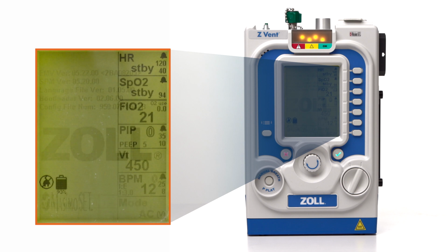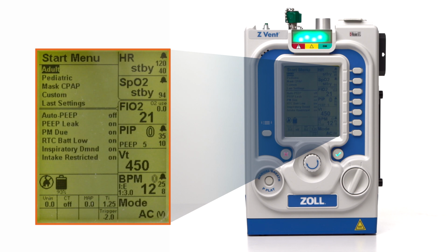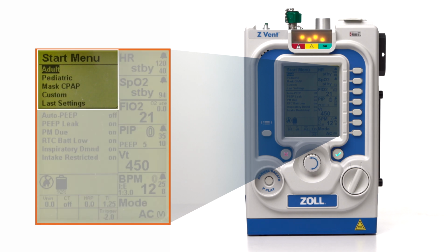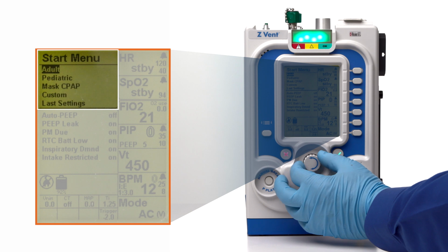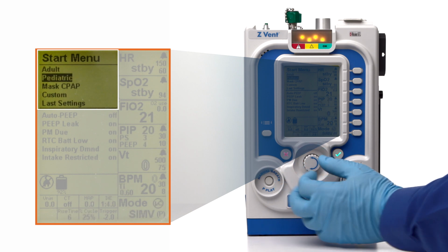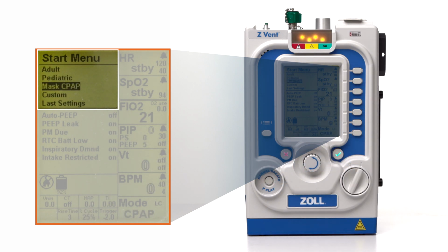If the self-check passes, the start menu will display on screen at the top left, and the LED array will alternate between yellow and green until a patient configuration is selected. The ventilator automatically mutes any potential alarms for 2 minutes to allow the user ample time to adjust any necessary settings. The start menu allows the user to choose between predefined default settings for specific patient types: adult, pediatric, or patients requiring mask CPAP.